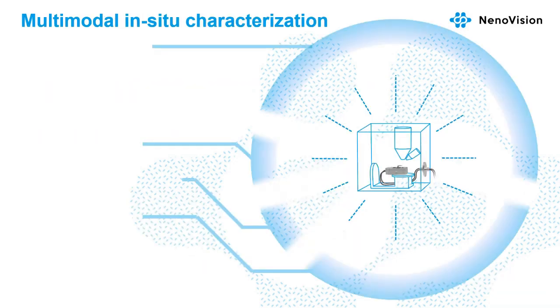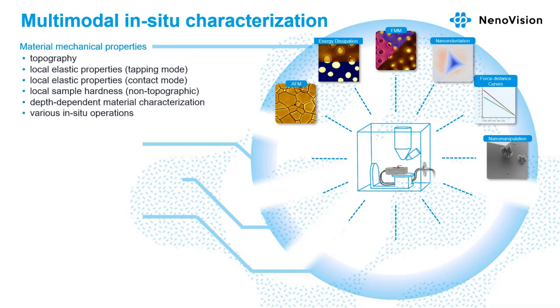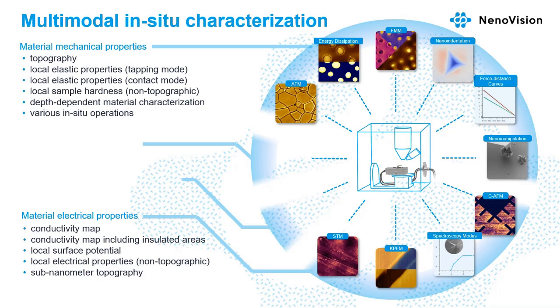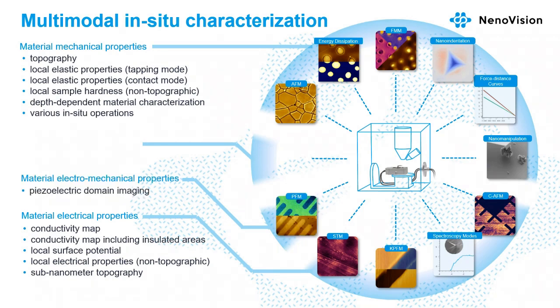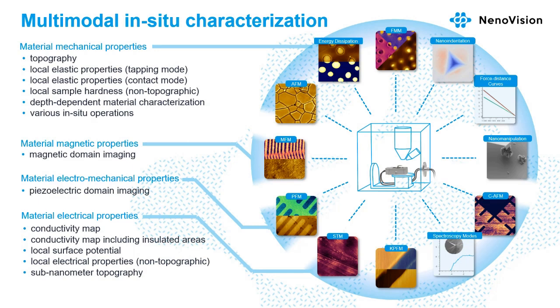LiteScope enables multimodal characterization. We divide the techniques into 4 groups. The first one is material mechanical properties, such as topography measurement or local elastic properties. The second one is the material electrical properties, so we can measure the conductivity of the sample surface or local surface potential or IV curves at one point. Then there is a group which combines mechanical and electrical properties together, and we have the piezo domain. So we measure piezoelectric domains, how they change in the material, and we are able to measure magnetic properties using MFM measurement.